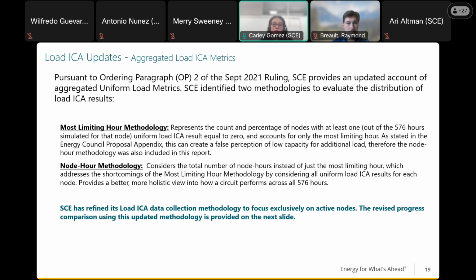The first methodology is the most limiting hour methodology. Results are aggregated via this method to represent a worst case scenario. In a nutshell, the minimum capacity outcome is selected, or in other words the most limiting hour, and this becomes the published ICA value for that segment. This is an extremely conservative view of circuit performance that doesn't capture behavior over time, since it reflects just the worst case hosting capacity at a single hour. As stated in the Energy Council proposal appendix, this methodology can sometimes create a false perception of low capacity for additional load.